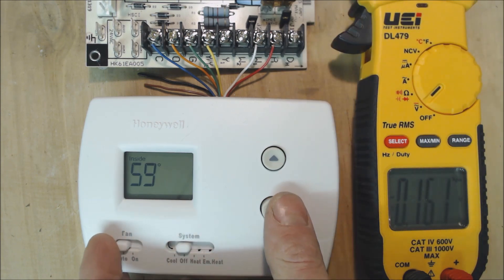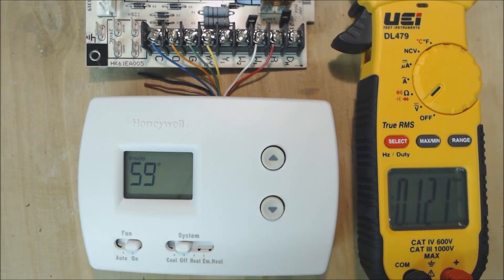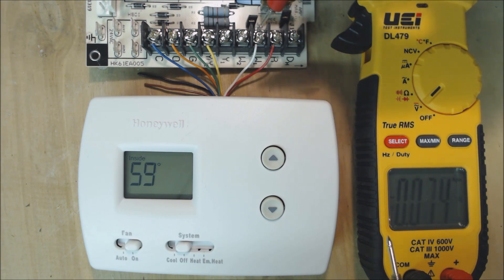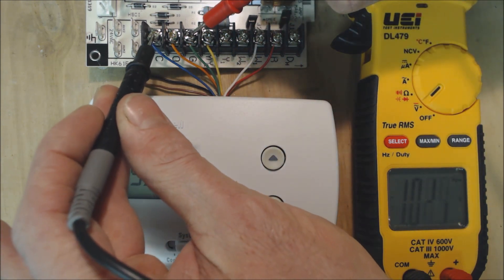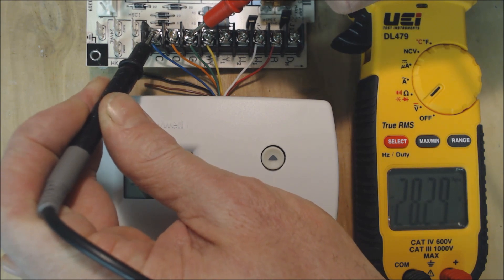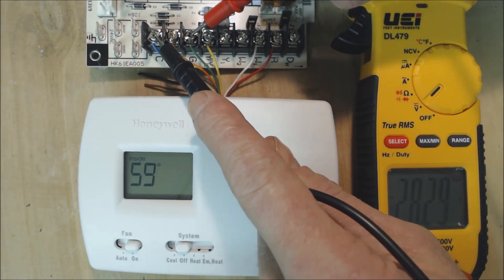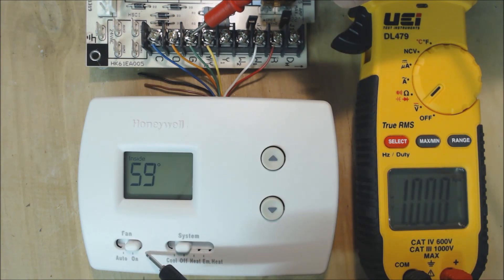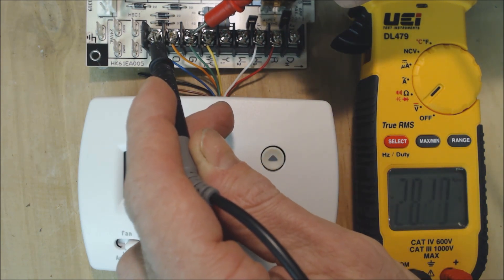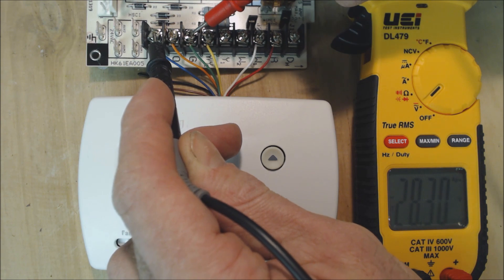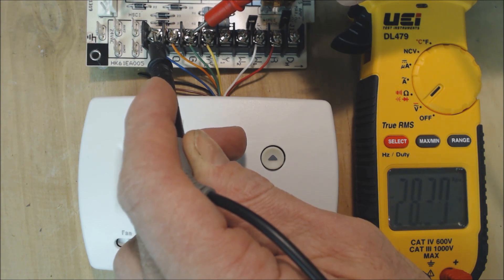Now let's go ahead and turn on the fan only. That means R is connected to G, and G is coming back. We should have 24 volts over here indicated by our 28 volts. We have 28 volts now because our fan is on. That's how we verify that our thermostat's actually working properly.